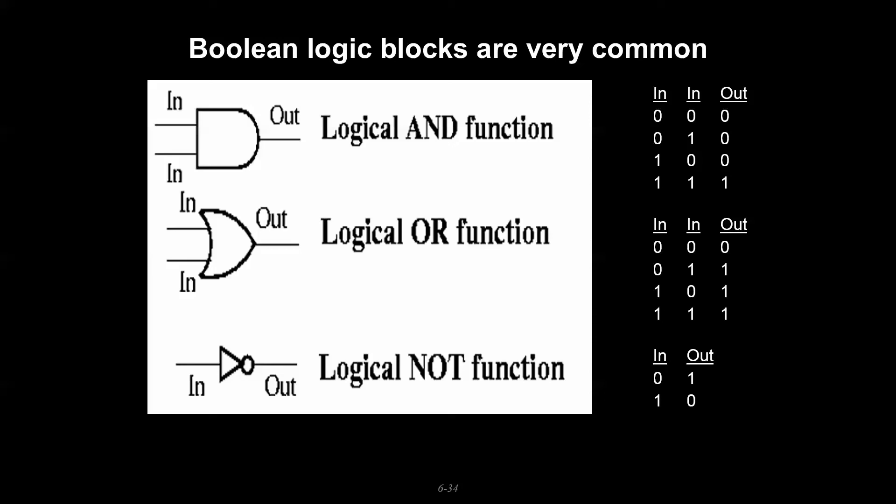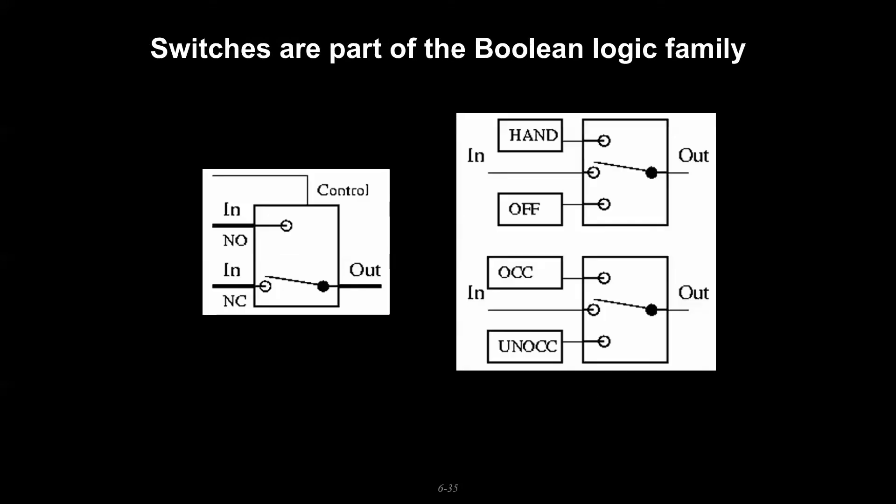Switches are also part of that Boolean logic block family, which is essentially an if/then statement. It has applications where you might see a hand-off-auto block where you're deciding if you're off in manual or hand, or passing through some control loop variable. Same thing with status information like occupied or unoccupied. Essentially what you're doing is giving this control block some type of criteria - if you're in this condition pass this, if you're in a different condition pass that.